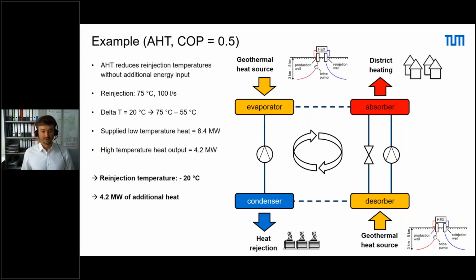If we have an example for the absorption heat transformer, we could look at such a setup where we have a reinjection temperature of 75 degrees, for example, without the heat transformer. And with the heat transformer, we could reduce the reinjection temperature, let's say by 20 degrees. That would mean that half of the heat that we extracted from the geothermal brine can now be used for the district heating. So we extracted 8.4 megawatts and can use 4.2 megawatts for the district heating. Of course, we have to have the heat rejection. On the other hand, if you want to use this reversible machine in summer and winter, we have to have heat rejection for the absorption chiller anyway. So this would also be in place already.